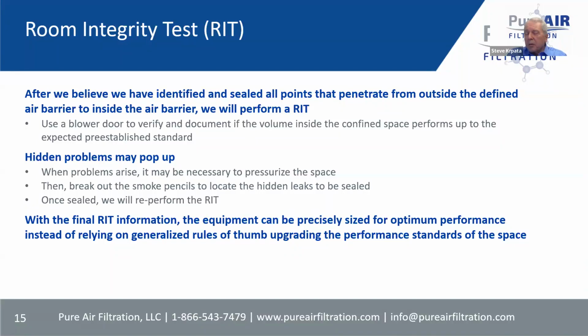As a standard practice, we do perform room integrity tests. We know what your target is for room pressurization. We would check different volumes of air to see what pressures are needed, what flow of air is needed to develop each pressure. And that helps us do a chart to figure out the validity of the data that we have. And if it's within certain established parameters, then we feel that we've sealed the room well.